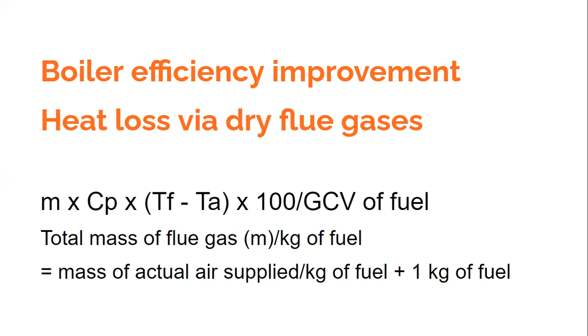By boiler tuning, I mean we need to adjust the supply air such that we have the maximum efficiency of the boiler. So for that we need to be very clear on the concepts. Look at this curve. There are certain terms which are written over here. One is called stoichiometric combustion.